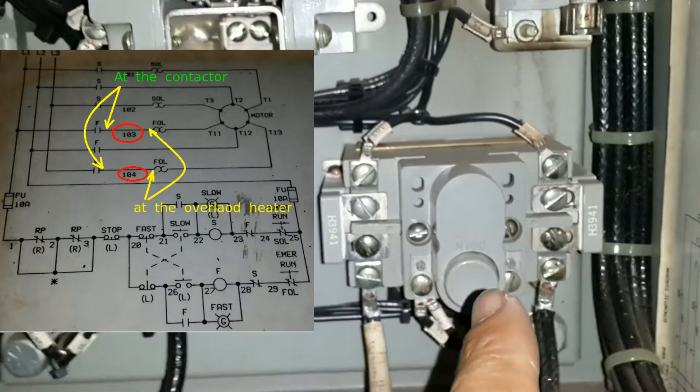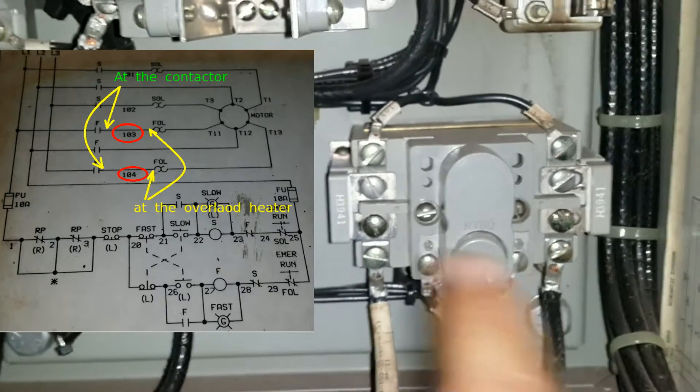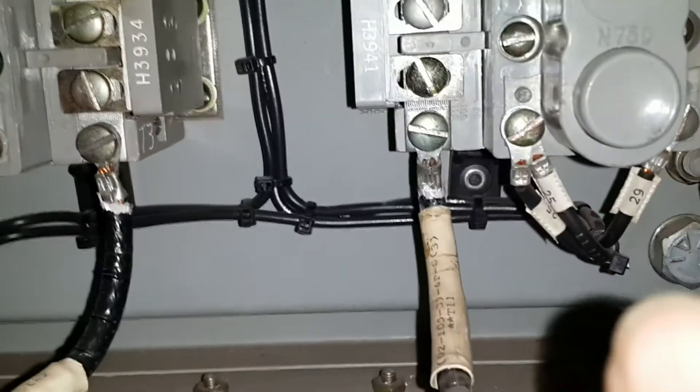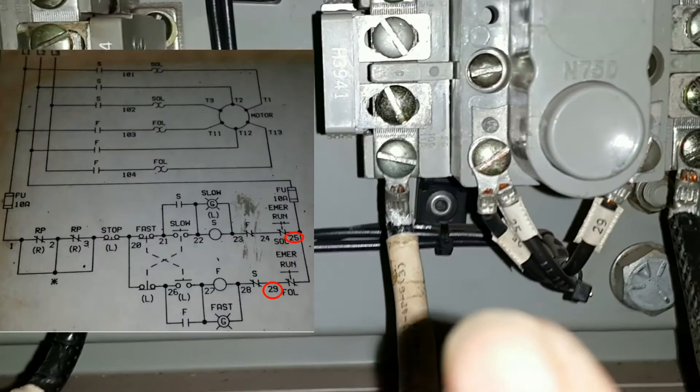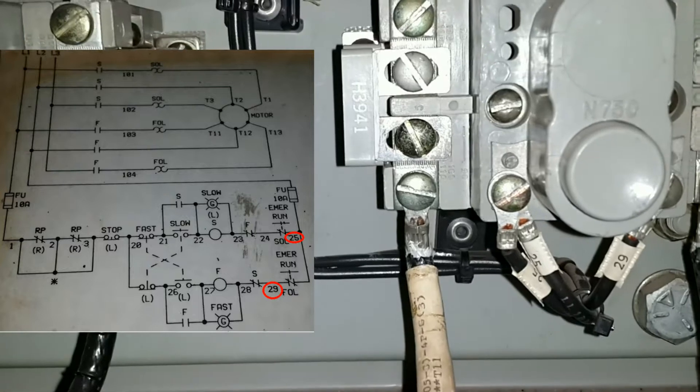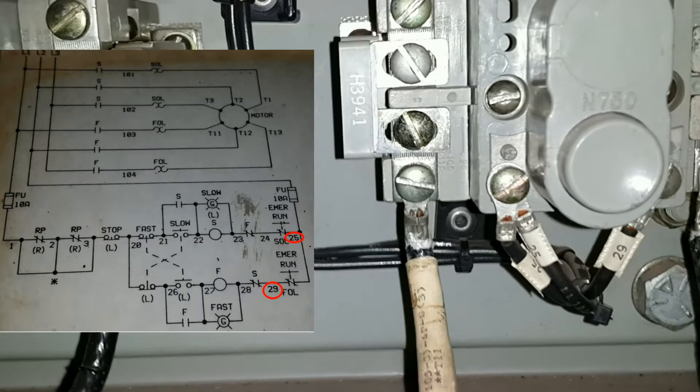And so this is the fast speed overload. Now another way to tell is by looking at this: look at that, that's 29 and 25. As you see on the left, those are the fast speed overload switches.